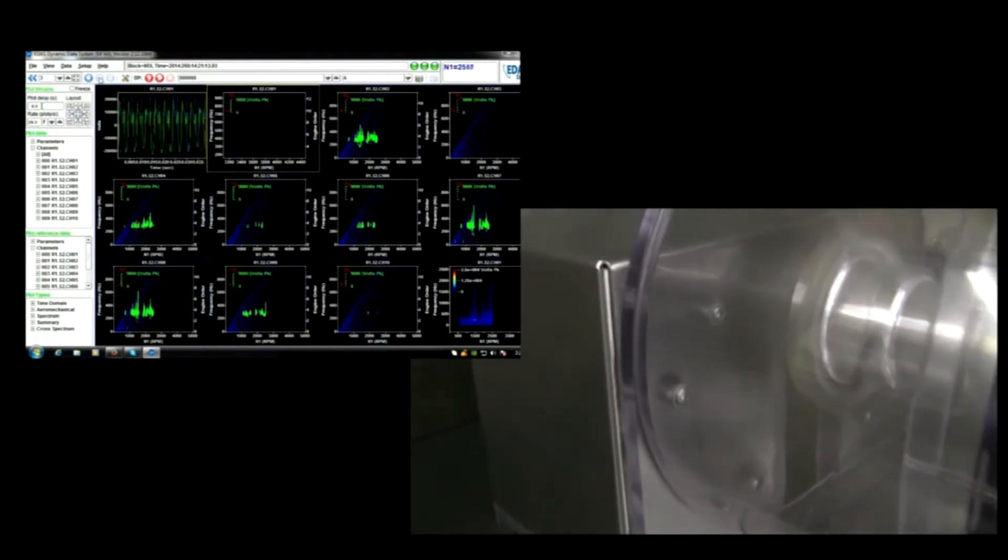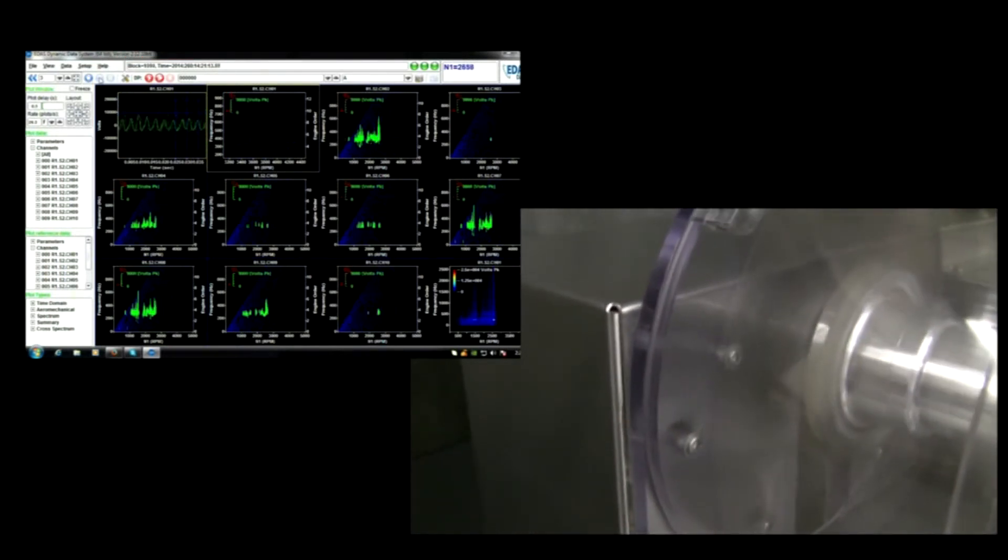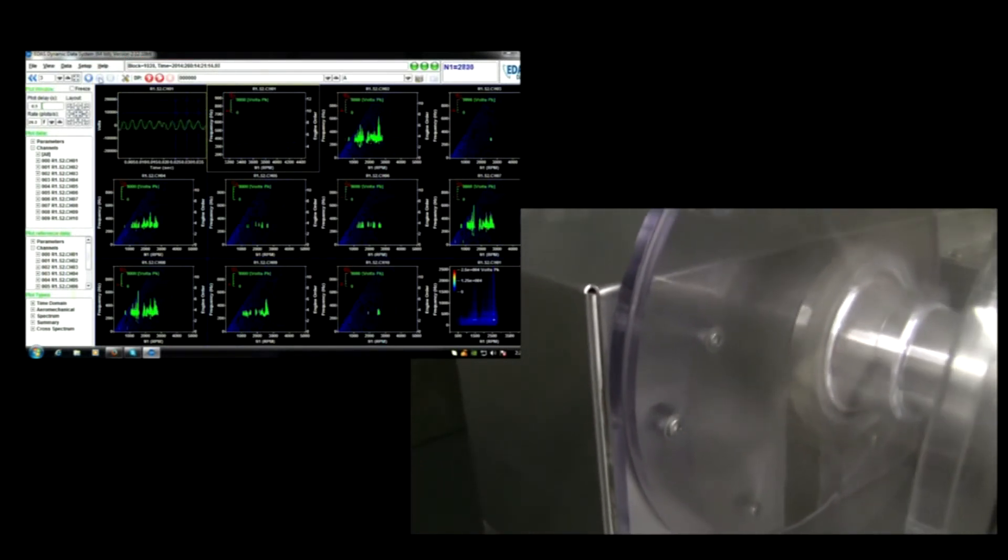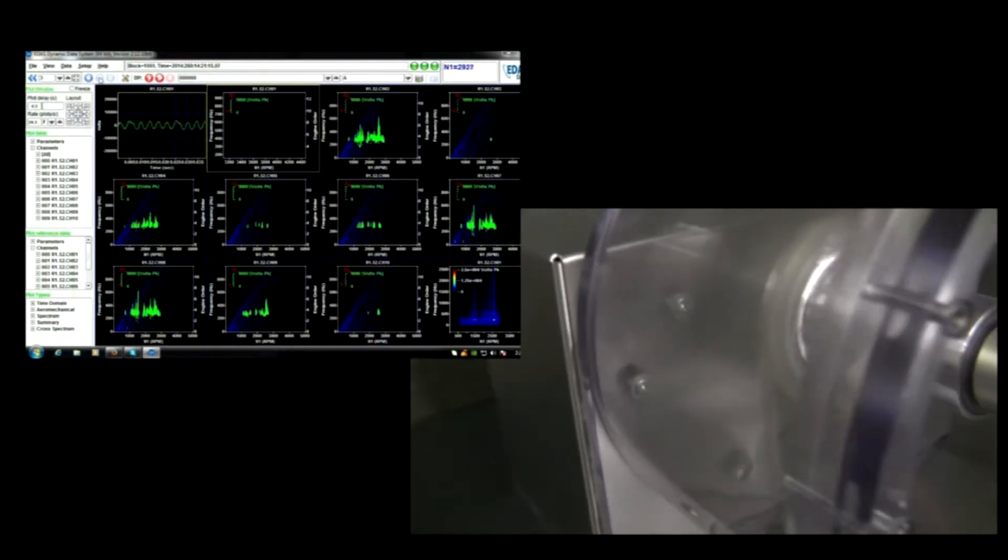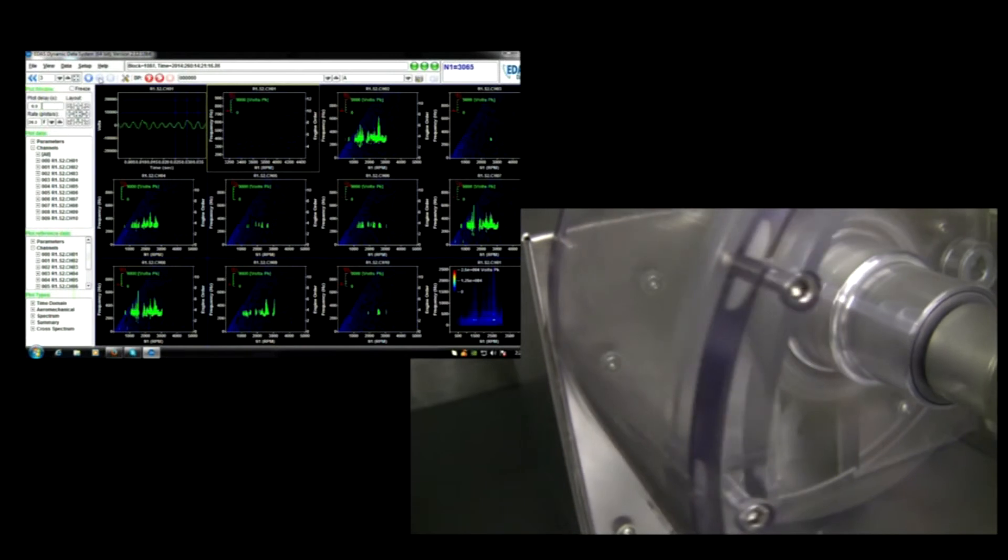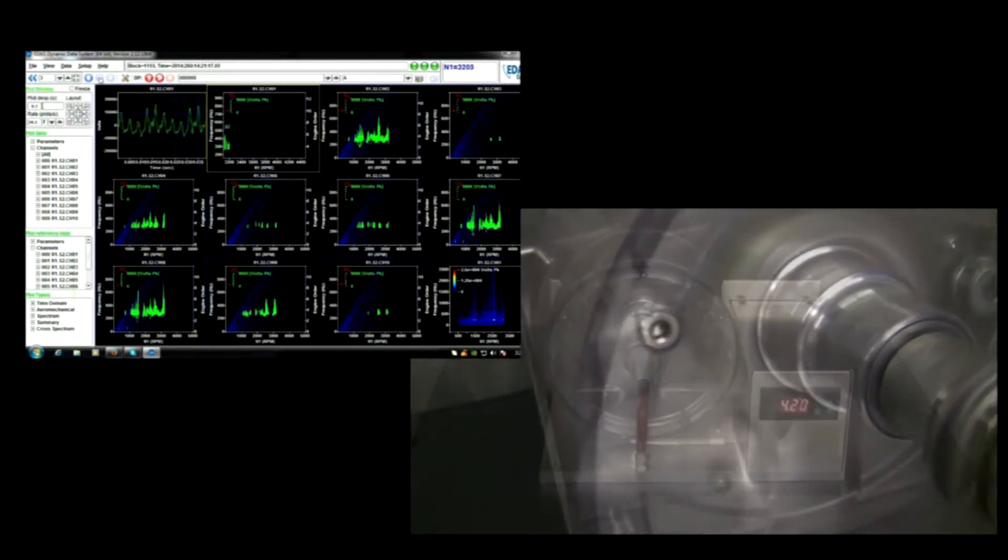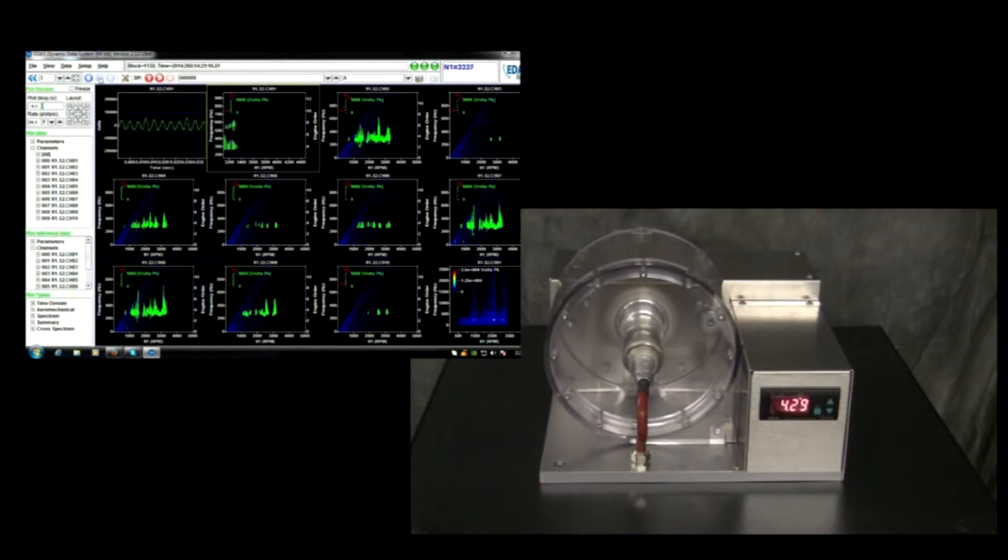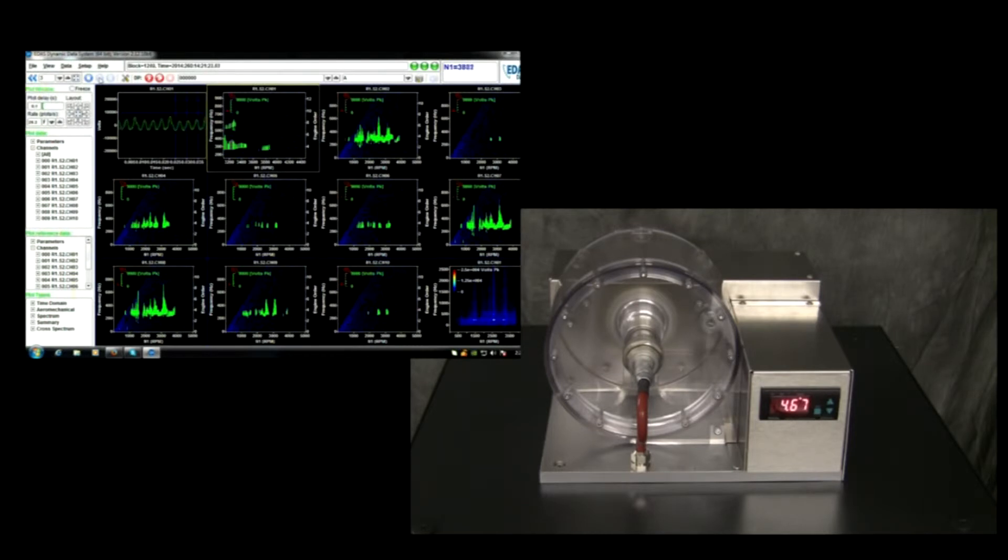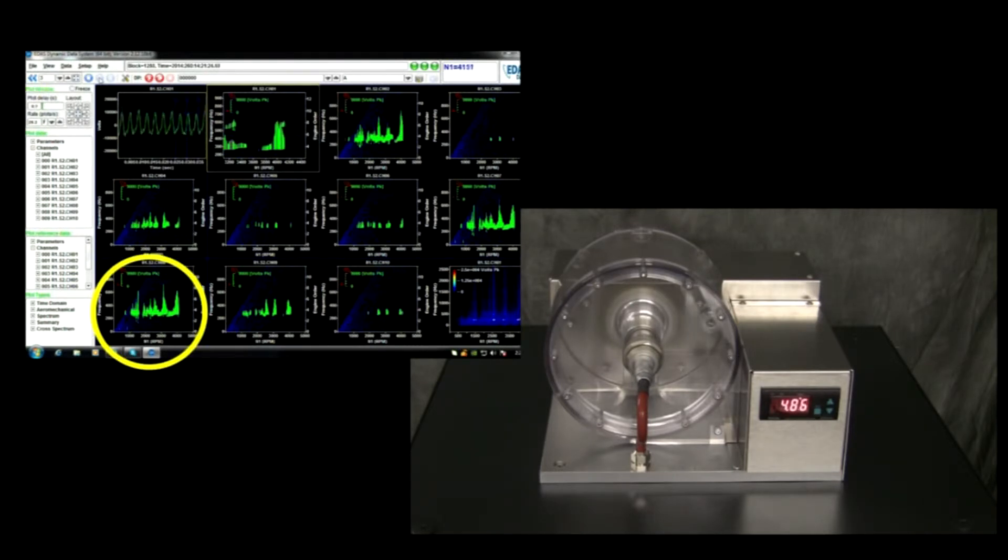All other diagrams shown will display real-time Campbell diagrams, which are displays of frequency against rotor speed. Tick marks are drawn on the diagrams with size proportional to the magnitude of vibration at a particular frequency.